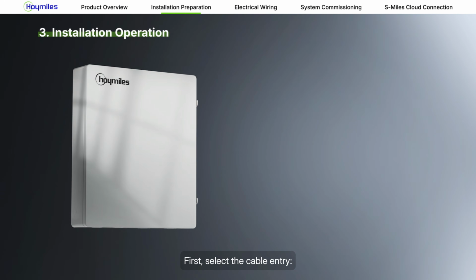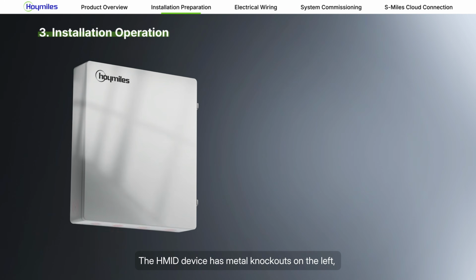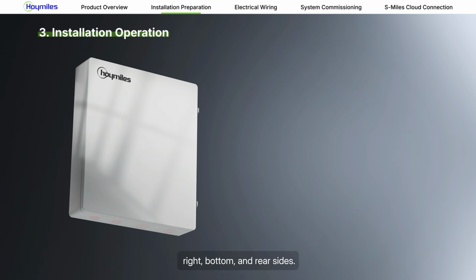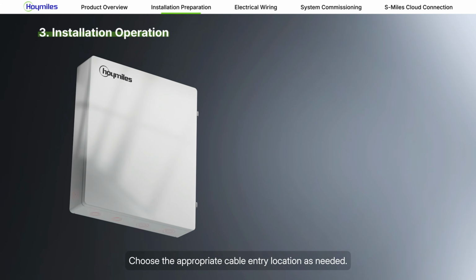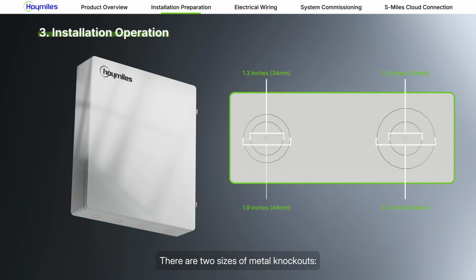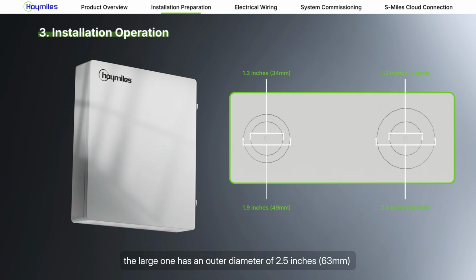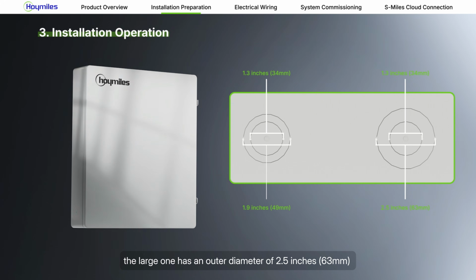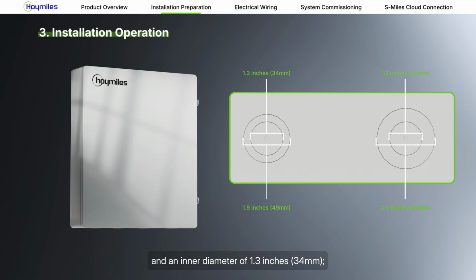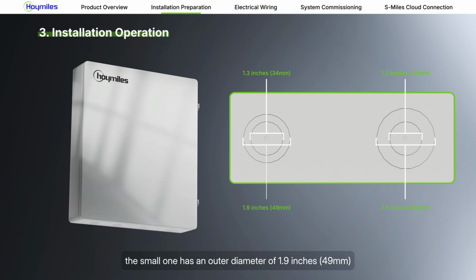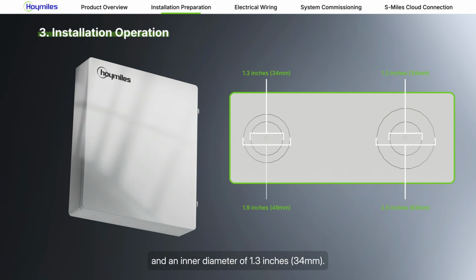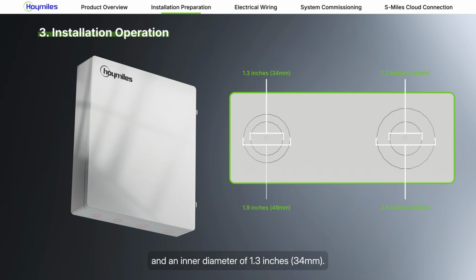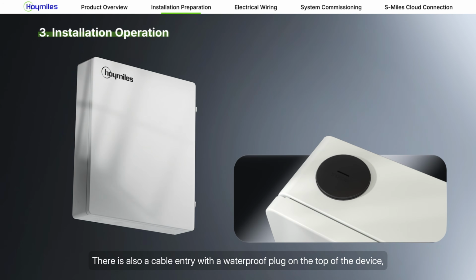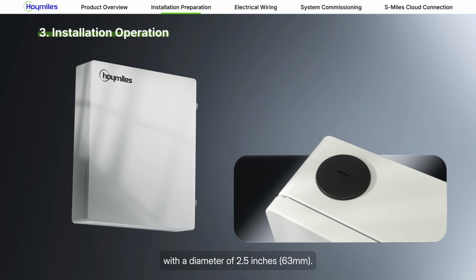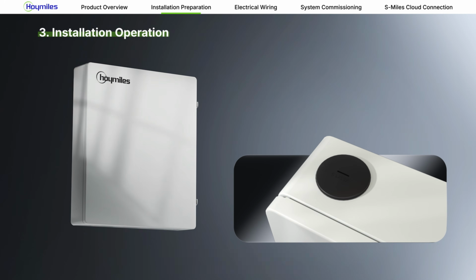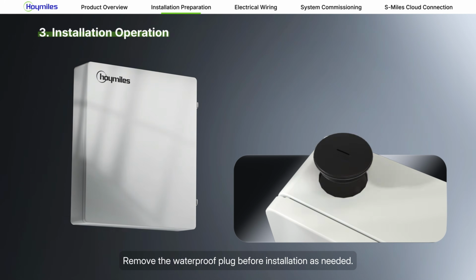First, select the cable entry. The HMID device has metal knockouts on the left, right, bottom, and rear sides. Choose the appropriate cable entry location as needed. There are 2 sizes of metal knockouts. The large one has an outer diameter of 2.5 inches and an inner diameter of 1.3 inches. The small one has an outer diameter of 1.9 inches and an inner diameter of 1.3 inches. There is also a cable entry with a waterproof plug on the top of the device, with a diameter of 2.5 inches. Remove the waterproof plug before installation as needed.